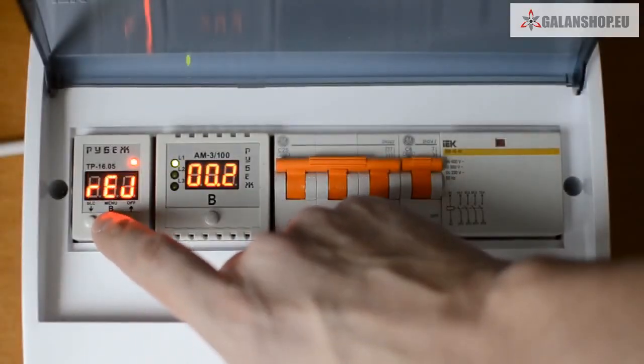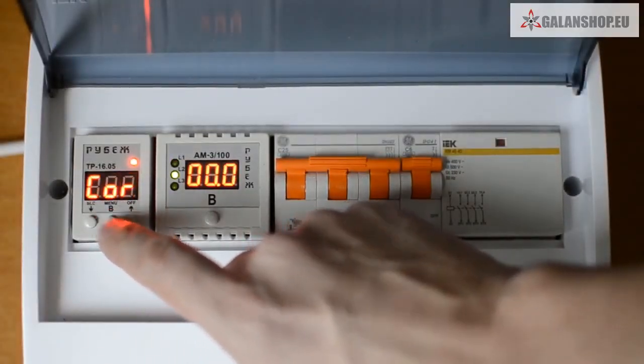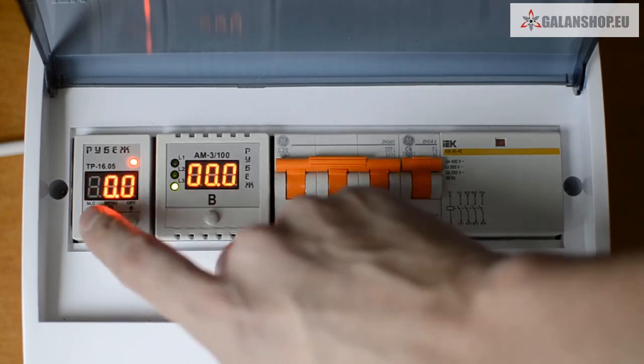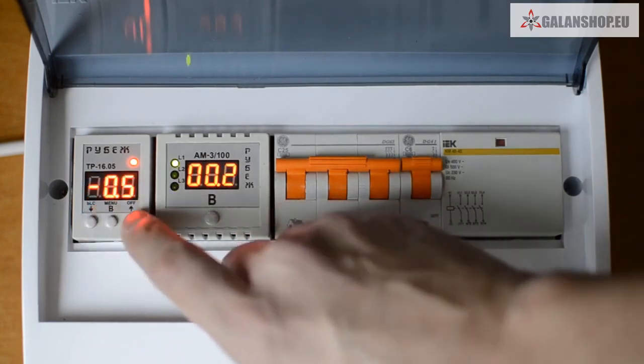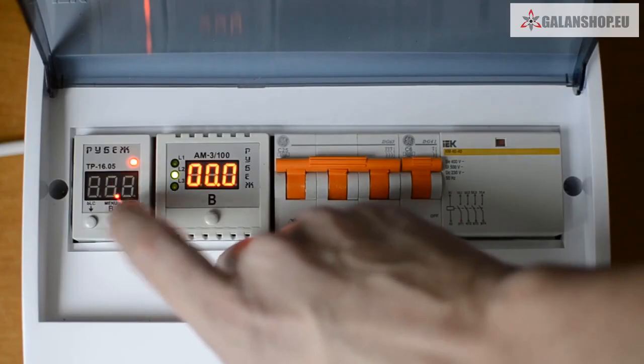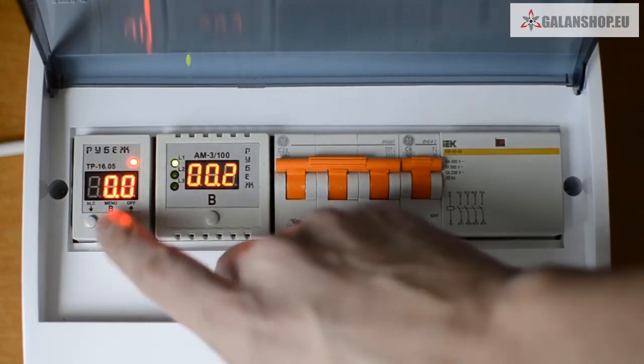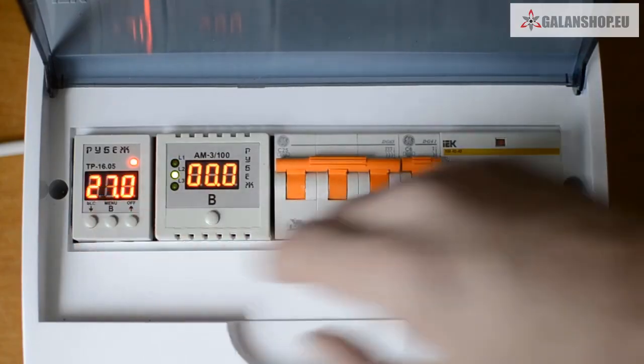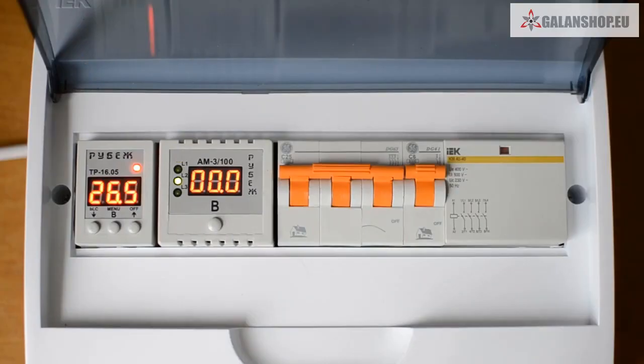Temperature sensor calibration. First, you need to access the controller's menu. To do it, press the B button and hold it for 2 seconds. Then press the same button shortly and choose a COR submenu. Use the down or up buttons to set a correction. The changeable value will blink. And press the B button shortly for confirmation.